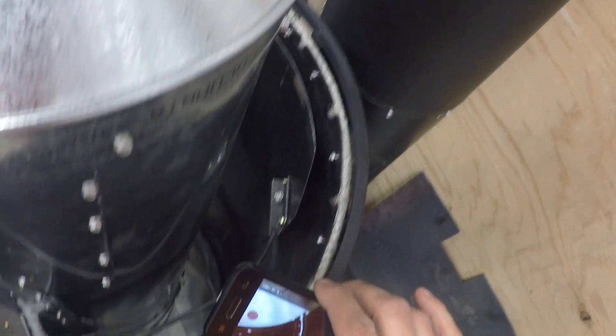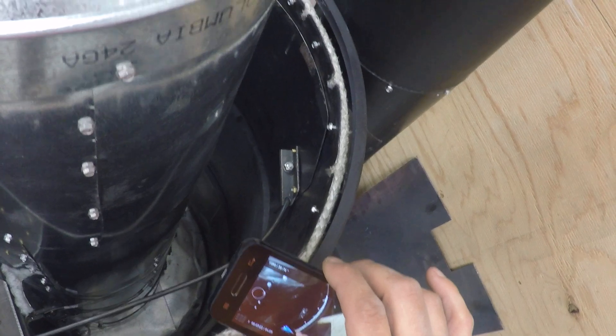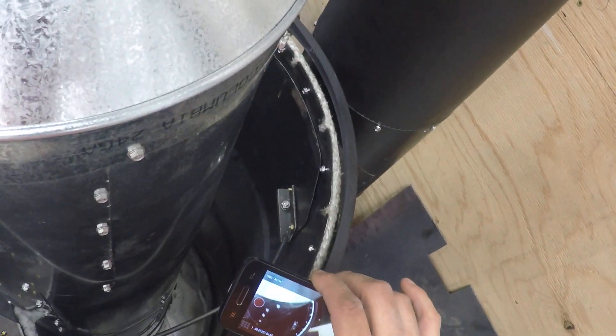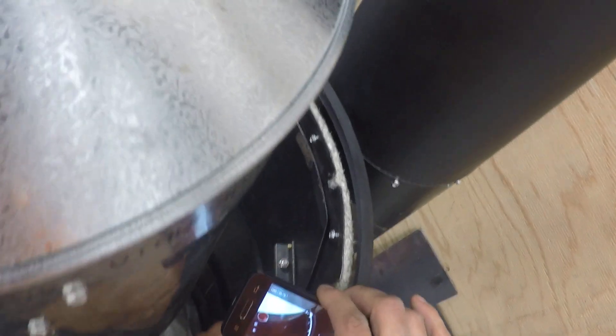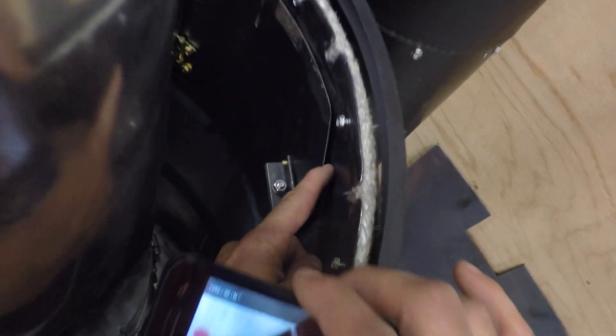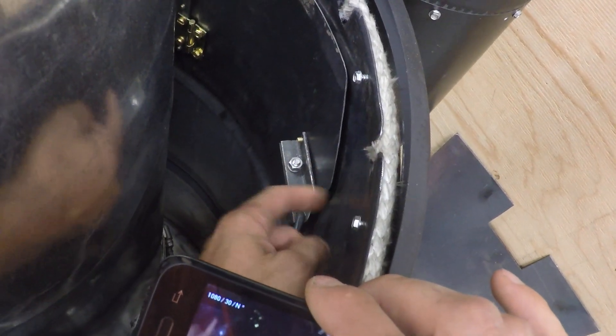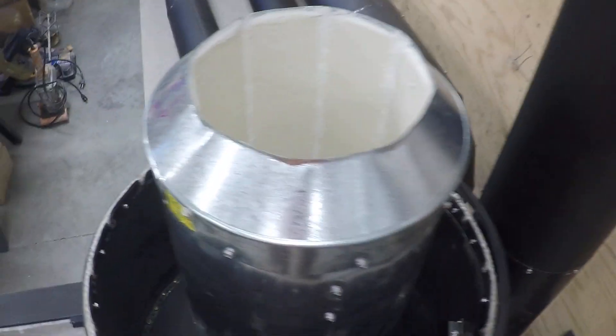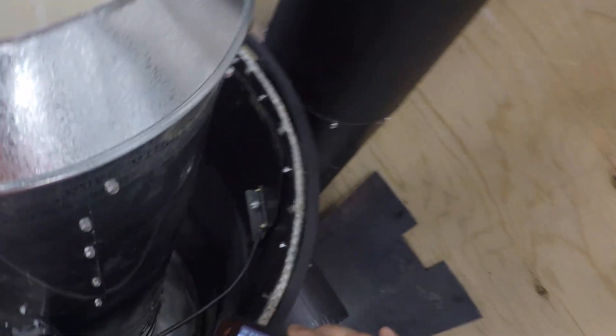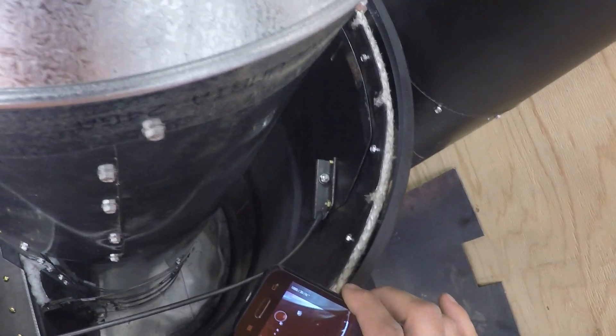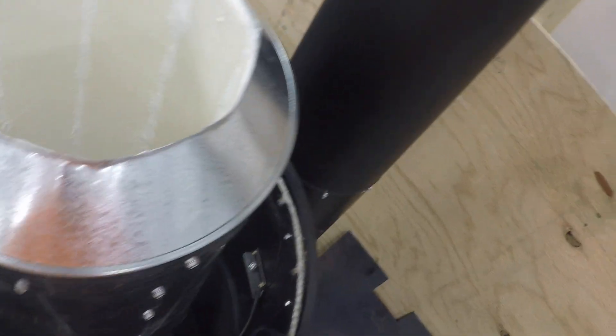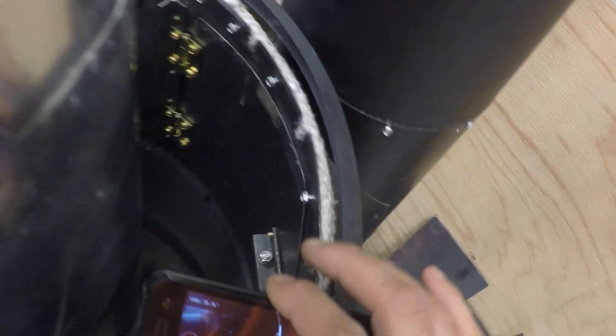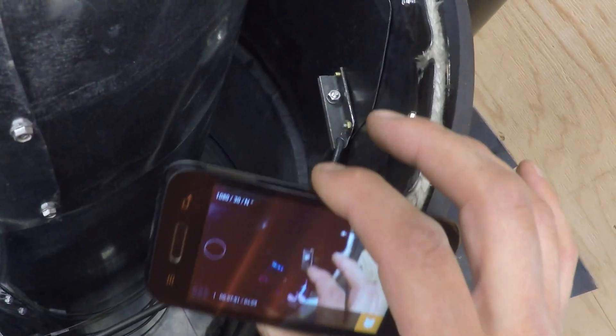So it has to be shut fairly well. When the system's running, if I have this to where it doesn't shut really well and I have this gap in here, you see this gap, that would suck in a lot of heat, making the system less efficient and shooting heat we don't want to shoot out the chimney. So we've got it kind of under spring tension. You push in, got a little latch that locks that door shut really well, and that'll give us a nice close-off when the system's running properly.